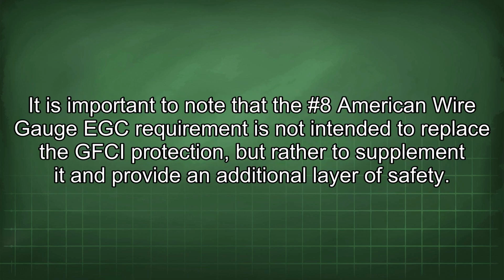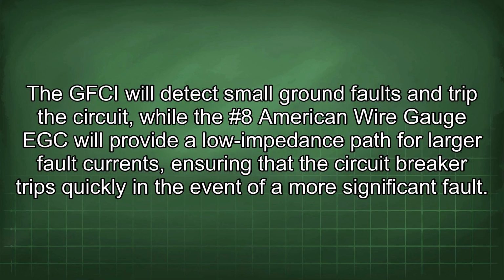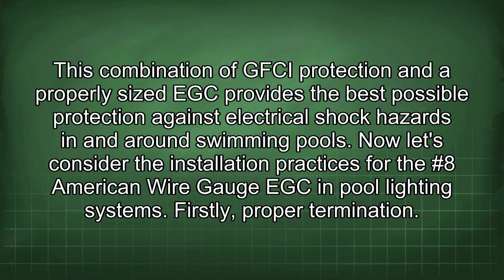It is important to note that the #8 American wire gauge EGC requirement is not intended to replace the GFCI protection, but rather to supplement it and provide an additional layer of safety. The GFCI will detect small ground faults and trip the circuit, while the #8 American wire gauge EGC will provide a low impedance path for larger fault currents, ensuring that the circuit breaker trips quickly in the event of a more significant fault. This combination of GFCI protection and a properly sized EGC provides the best possible protection against electrical shock hazards in and around swimming pools.